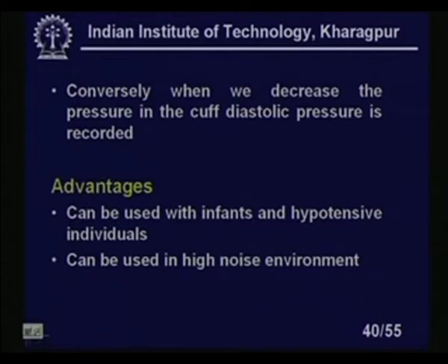It can be used in a high noise environment, because with all these other measurement techniques, the physician must locate the time when the valves are opening. They must locate the barometric pressures, the manometric pressures when the valves are opening, right. So, it is sometimes very difficult in a noisy environment. So, it is quite immune to outside noise, environmental noise, which is very common in hospitals. So, it can be nicely utilized in that type of environment.